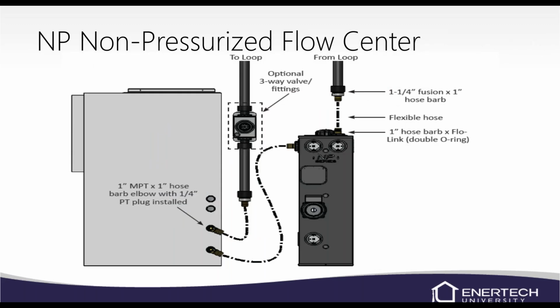There's a little bit closer up view. That does have a double O-ring fitting from your loop field, and then a double O-ring fitting to your unit, with a couple other Flo-Link or double O-ring fittings right above these three-way valves so that you can flush. So if you have the NP, you only would need the one flush block for the unit itself. When we flush a non-pressurized circuit, we never want to flush through the flow center itself. The flow center has PVC in it, and we run the risk of breaking that PVC. So we never flush through the unit or the flow center on a non-pressurized system.